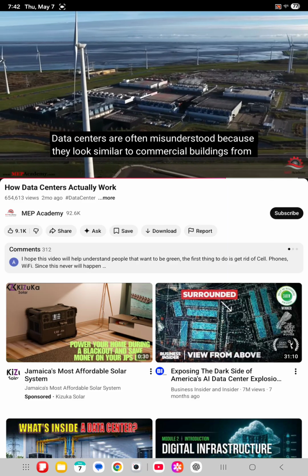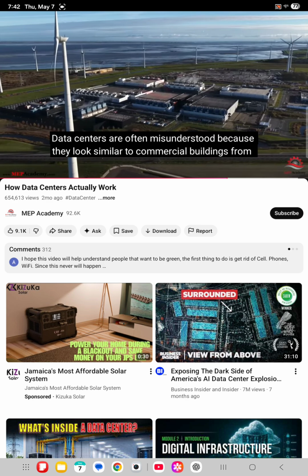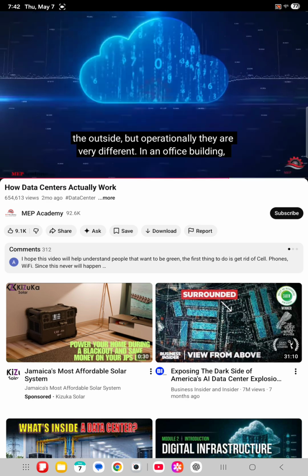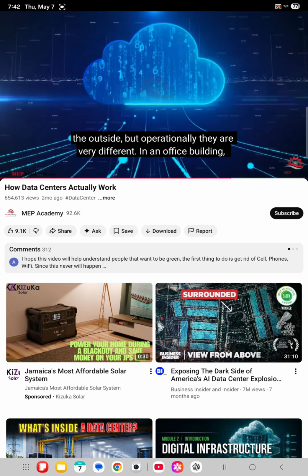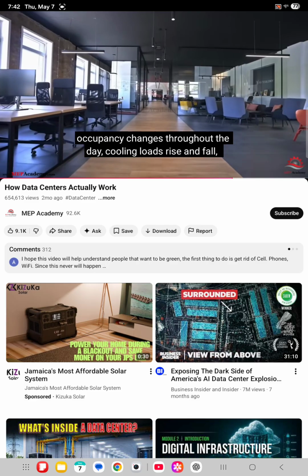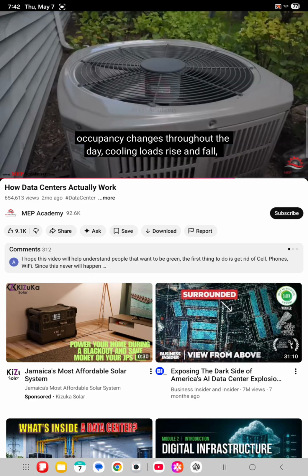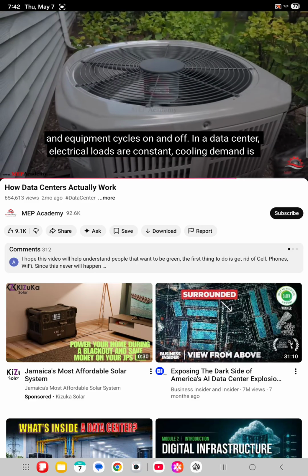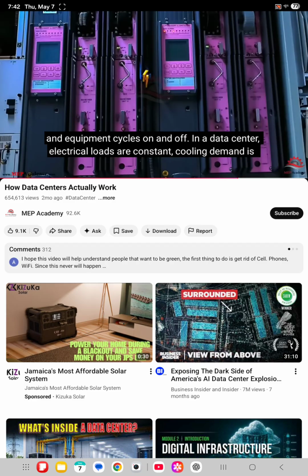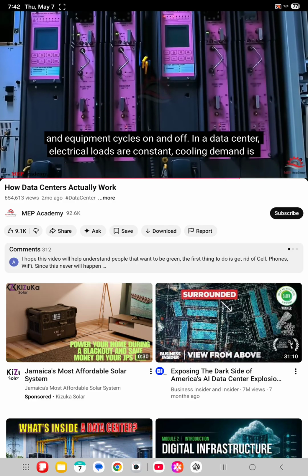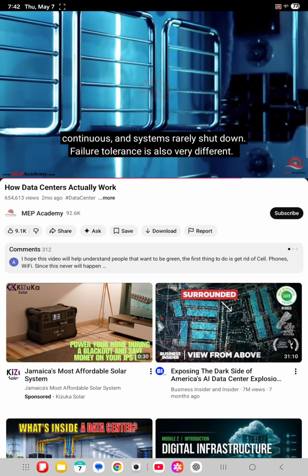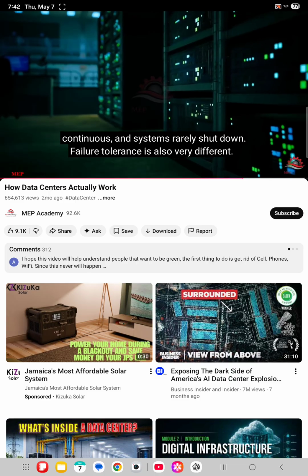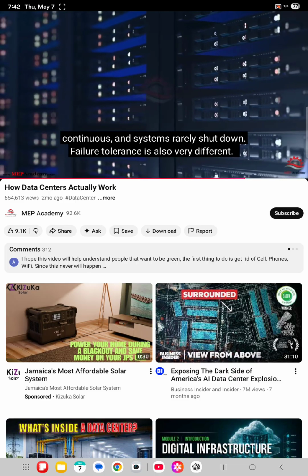Data centers are often misunderstood because they look similar to commercial buildings from the outside, but operationally they are very different. In an office building, occupancy changes throughout the day. Cooling loads rise and fall, and equipment cycles on and off. In a data center, electrical loads are constant. Cooling demand is continuous, and systems rarely shut down. Failure tolerance is also very different. I could start right there.